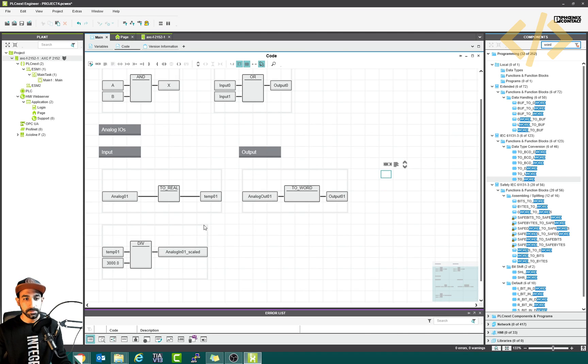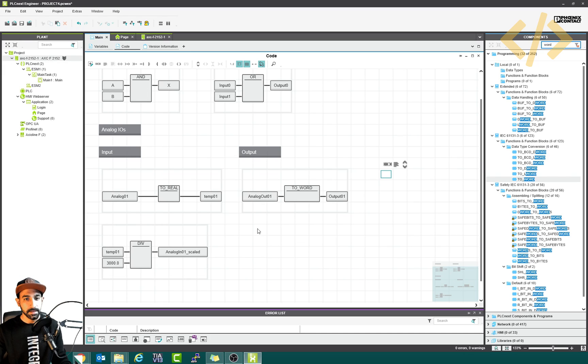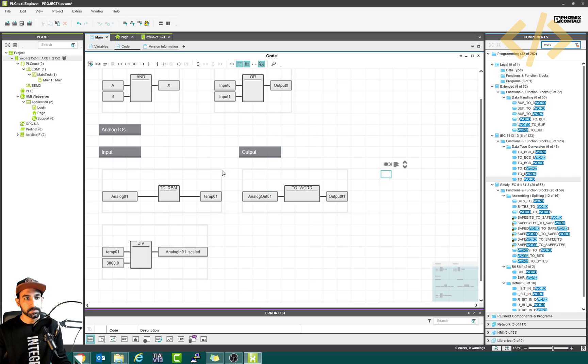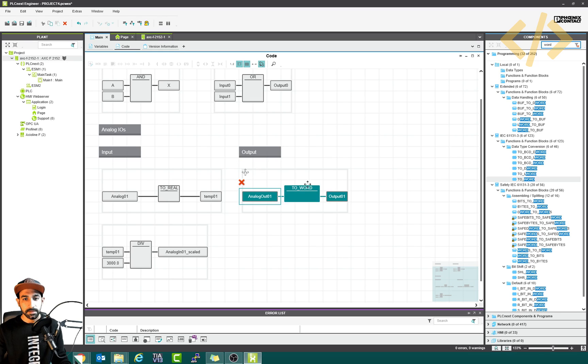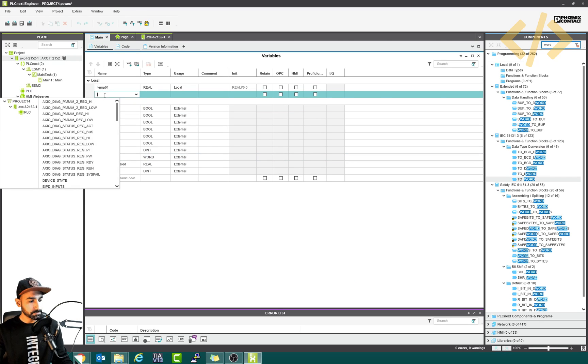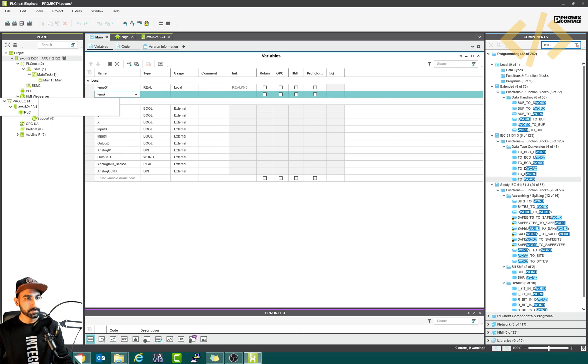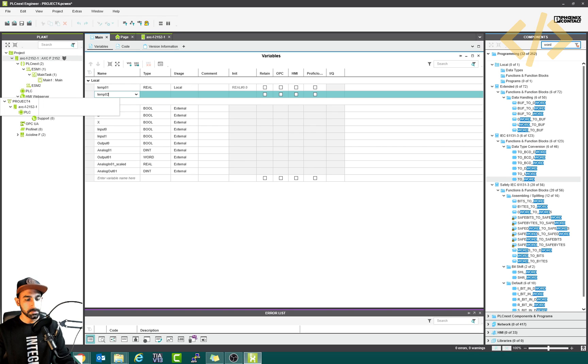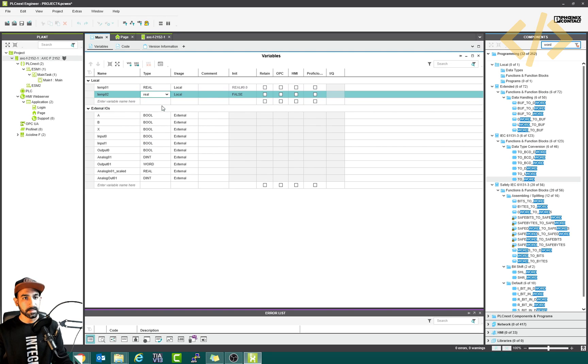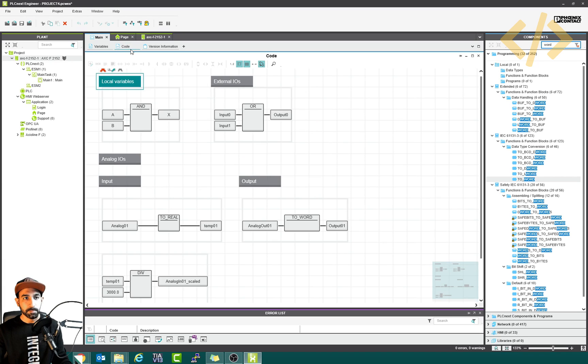If you also want to show the value on the HMI, we can also do that. So in this case, we convert this out 01 to real and then divide by 3000 and we can get a scale output. We can do that very quickly. So I will first take another temporary variable because we have to work with the real. So I will type temp 02. This should be real, also local.